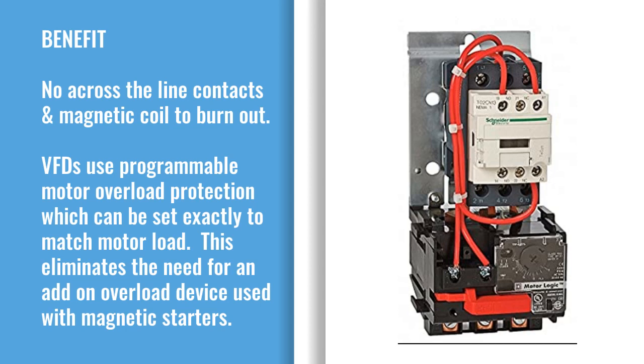VFDs use programmable motor overload protection, which can be set exactly to match motor load. This eliminates the need for an add-on overload device used with magnetic starters.